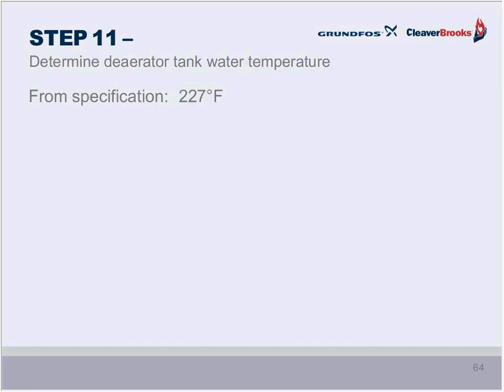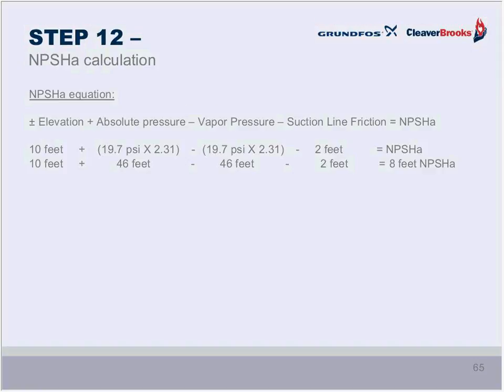Next, we need to worry about the temperature in the source tank. In this case, we're using a deaerator tank at 227 degrees F. This helps us in making an NPSH calculation. Net positive suction head available, and that's a source of another course if you'd like to come to one of those. We take our elevation on our suction side. We do some math with the absolute pressure and the vapor pressure. We subtract some suction line friction, and we find out how much net positive suction head available is forcing water into the eye of the impeller. And in this case, it's 8 feet. That's the value we have to be able to deal with.